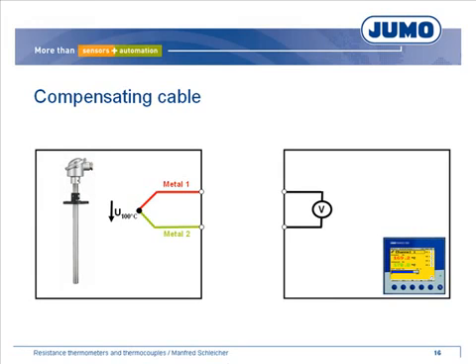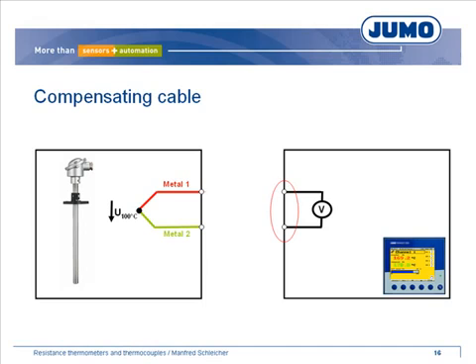So far we assumed that the thermocouple is directly connected to the device, but often connection cables are necessary. For internal temperature compensation, the second thermoelectric voltage has to occur on the terminals of the field device. Therefore, a compensation cable must be used for the connection, which has to have the same thermoelectric characteristics as the metals of the thermocouple. The reference junction results in the field device, and the internal PT100 measures the temperature of the reference junction so the measurement result is corrected.